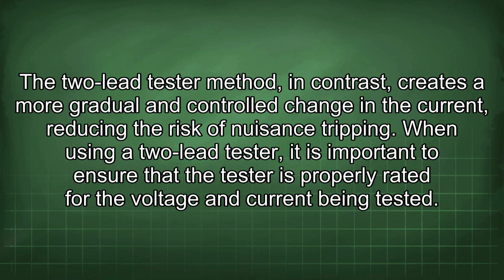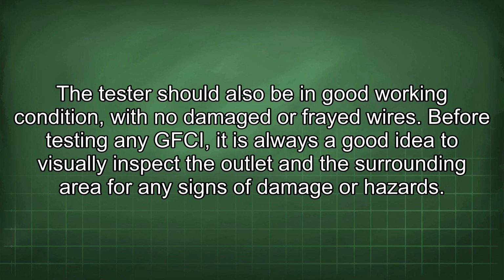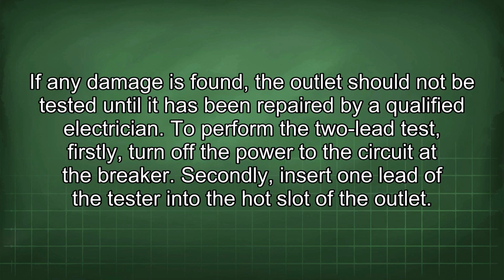When using a 2-lead tester, it is important to ensure that the tester is properly rated for the voltage and current being tested. The tester should also be in good working condition with no damaged or frayed wires. Before testing any GFCI, it is always a good idea to visually inspect the outlet and the surrounding area for any signs of damage or hazards. If any damage is found, the outlet should not be tested until it has been repaired by a qualified electrician.